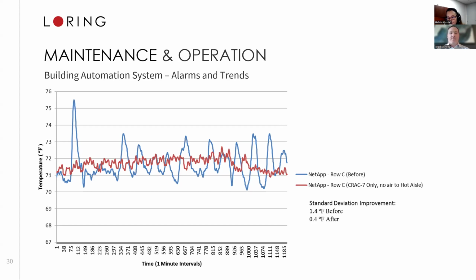So this is an example of a study we did at a data center that was put into a historic courts building in DC. And that blue trend line represents the temperature profile in the room prior to any corrective actions being taken. You can see there's big spikes and troughs in that trend line. Each of those is going to impose stress on the operation of the system. So every time you see the trend line drop, that's the temperature dropping because the compressor kicked on. And then it maintains for a while, then it spikes up and then drops again. And every time that drop happens in this trend period is added stress on the compressors for the system, because it's going on and off and on and off.